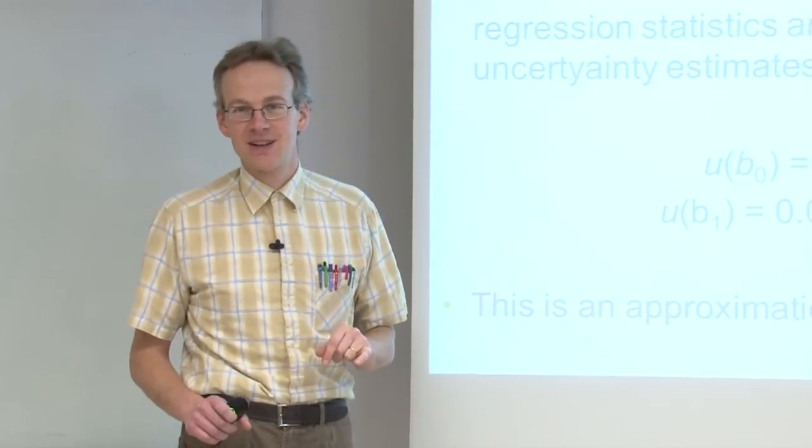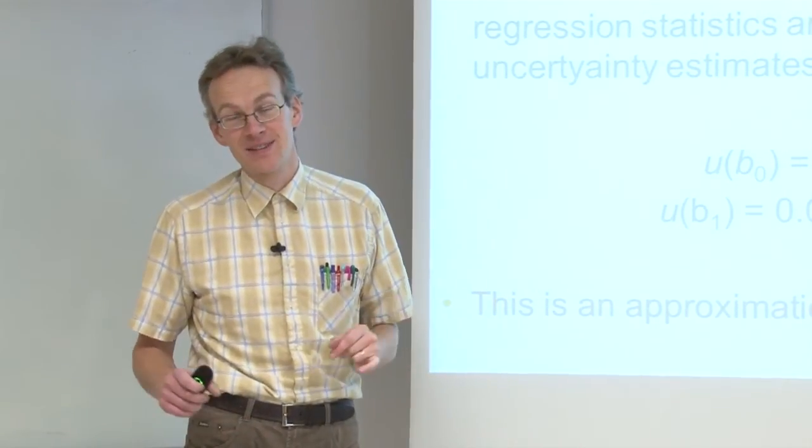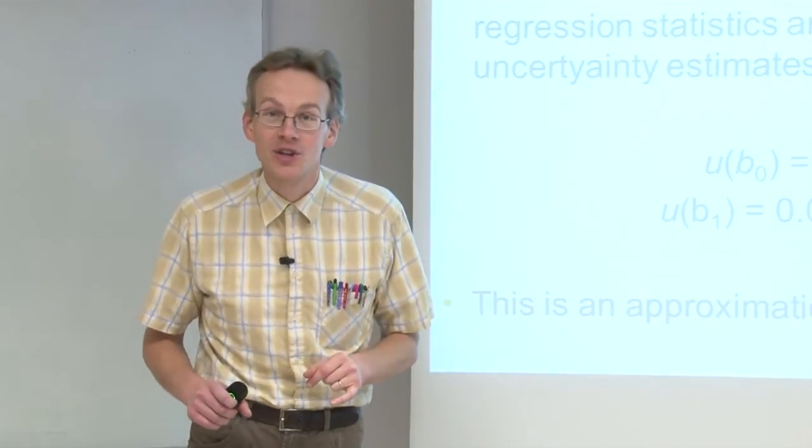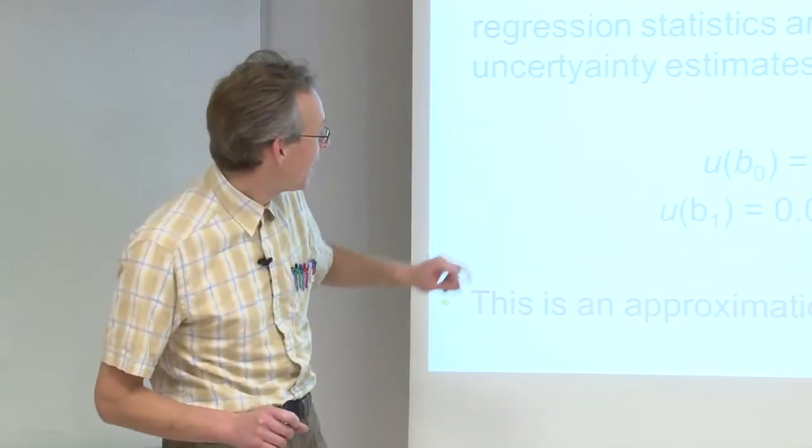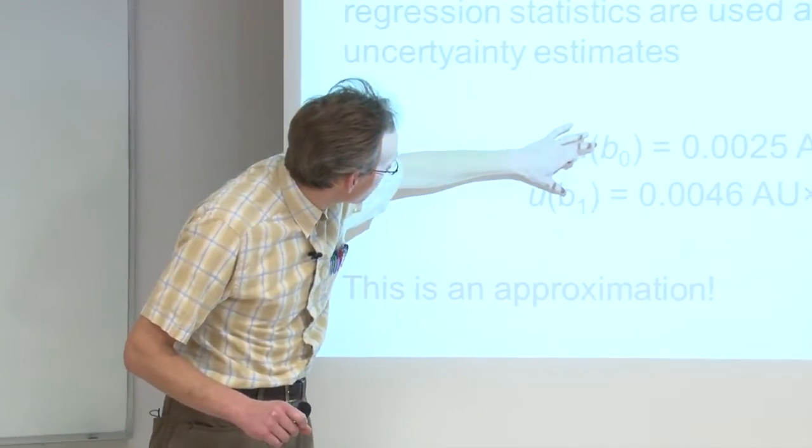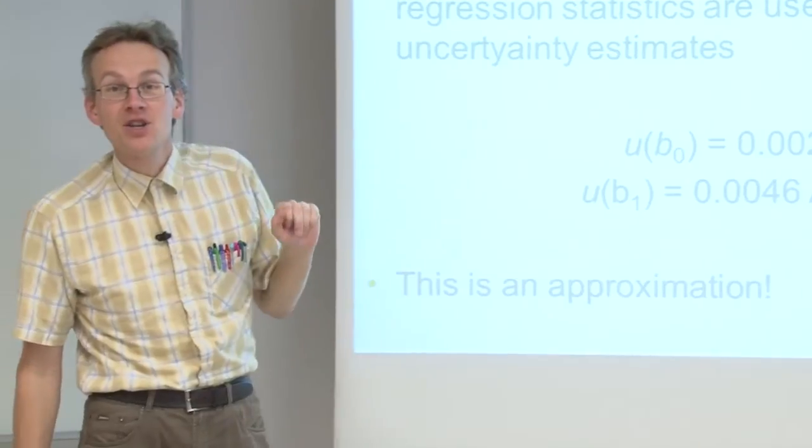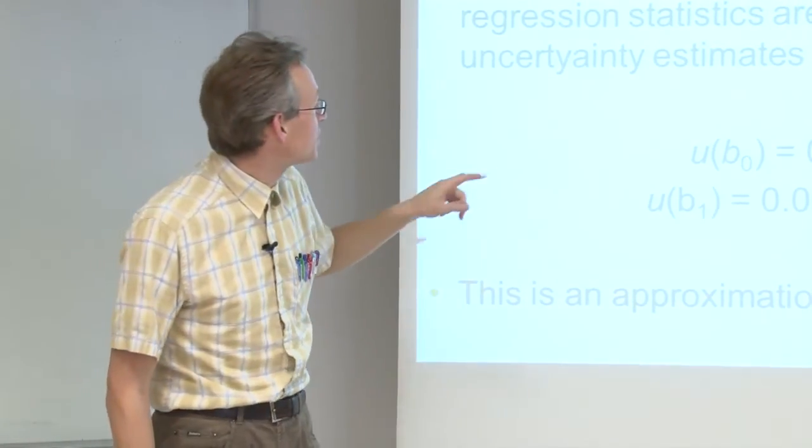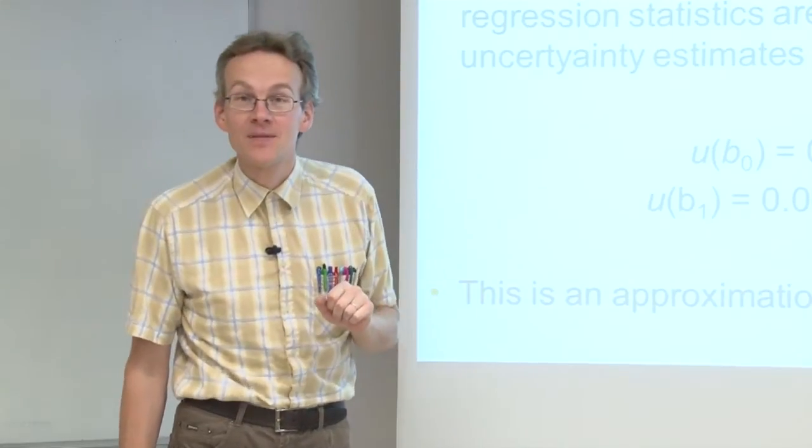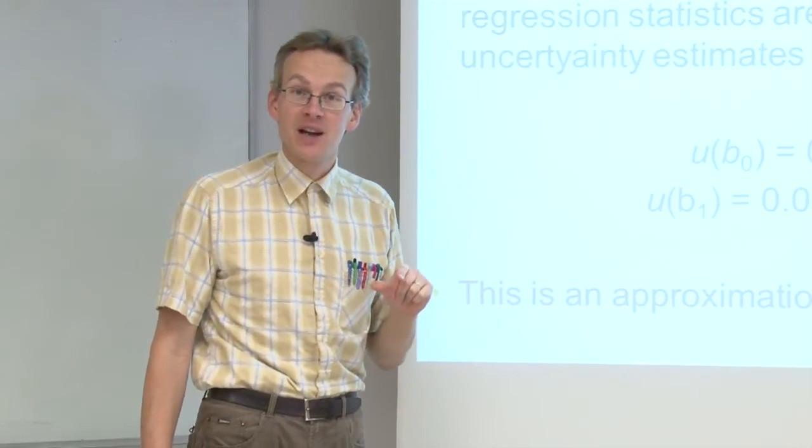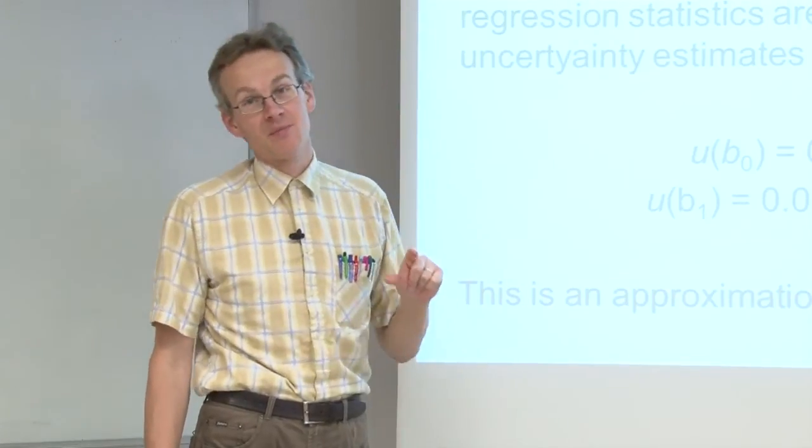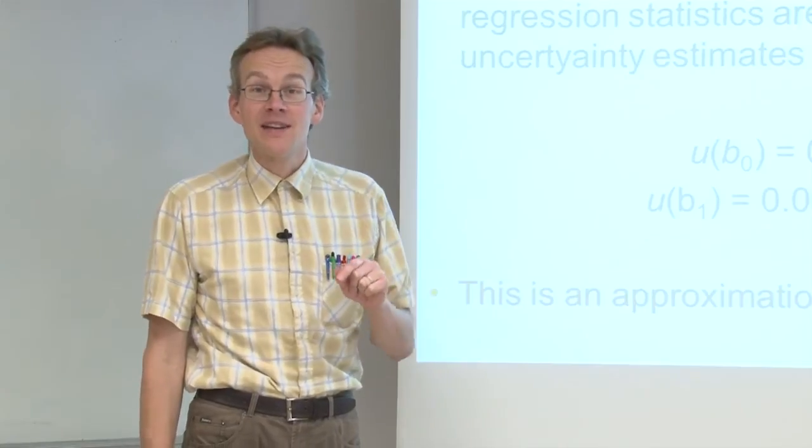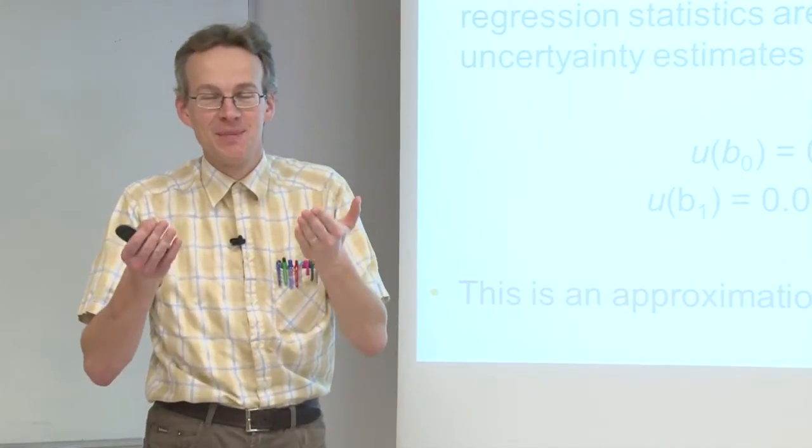Slope and intercept of the same calibration line are always slightly correlated. But this correlation is a negative correlation, meaning if one of them becomes higher, the other one becomes lower. If a negative correlation is left out of consideration, then we slightly overestimate the uncertainty.